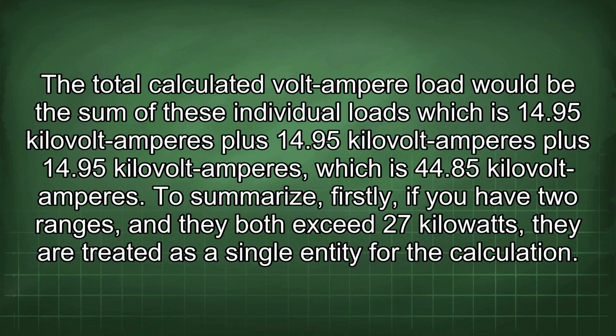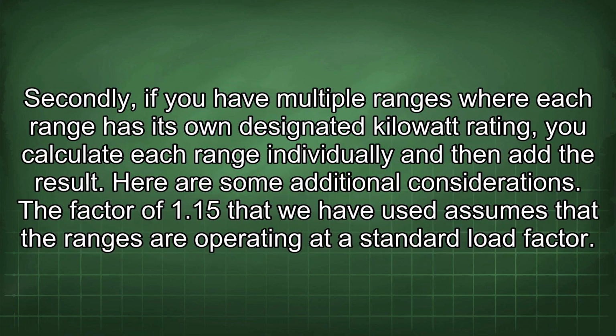To summarize, firstly, if you have two ranges and they both exceed 27 kilowatts, they are treated as a single entity for the calculation. Secondly, if you have multiple ranges where each range has its own designated kilowatt rating, you calculate each range individually and then add the results. Here are some additional considerations.